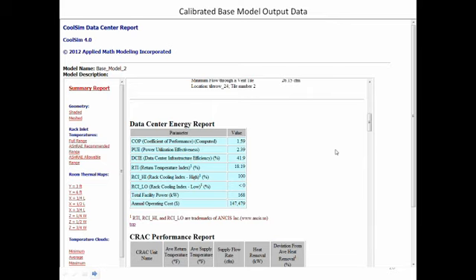report. Now, here we're calculating the COP, PUE. We also give you DCIE, which is just the inverse of PUE, RTI, which we talked about earlier, RCI, high and low, total facility power, and annual cost. So during the setup of the CoolSim model, you have the opportunity to enter information into the model about either readings or assumptions you're making associated with this data center, such as cost of electricity, and it will calculate these metrics for you. So it's a nice way to get away from hand calculations and have it be done by the program so that you can present it like this to your boss, your friends, your customers, whoever.